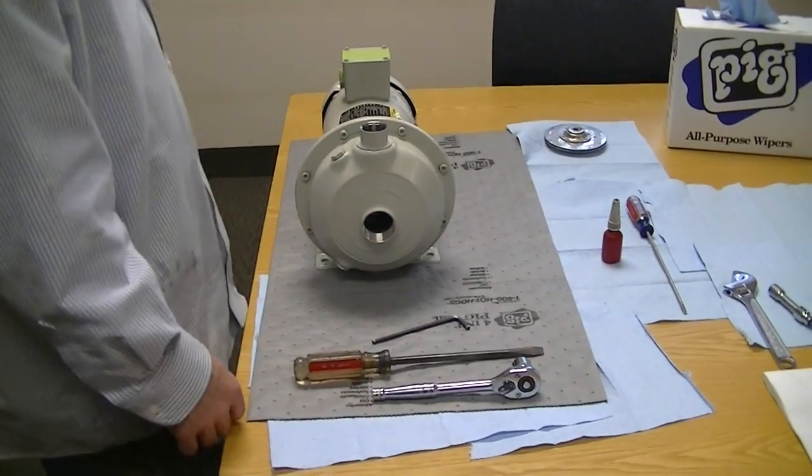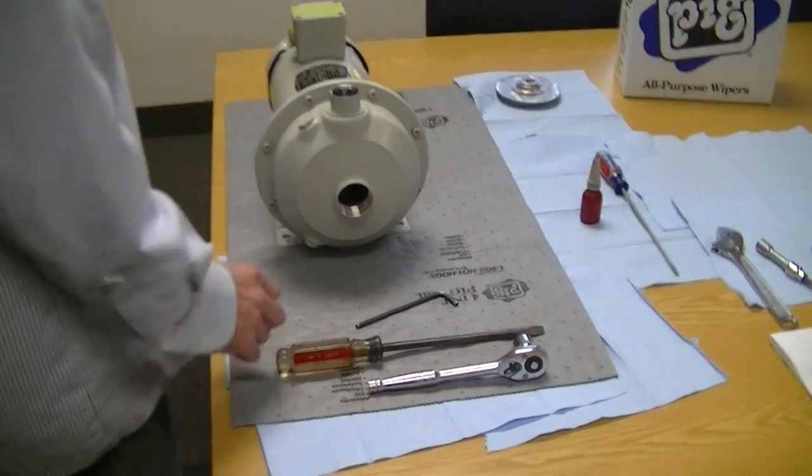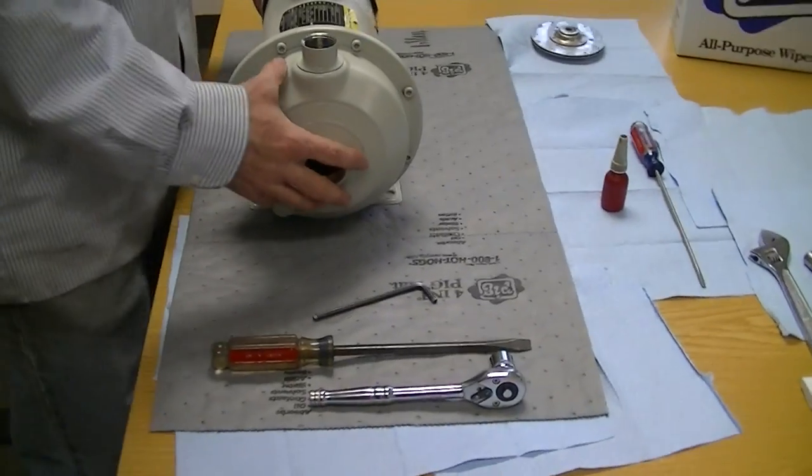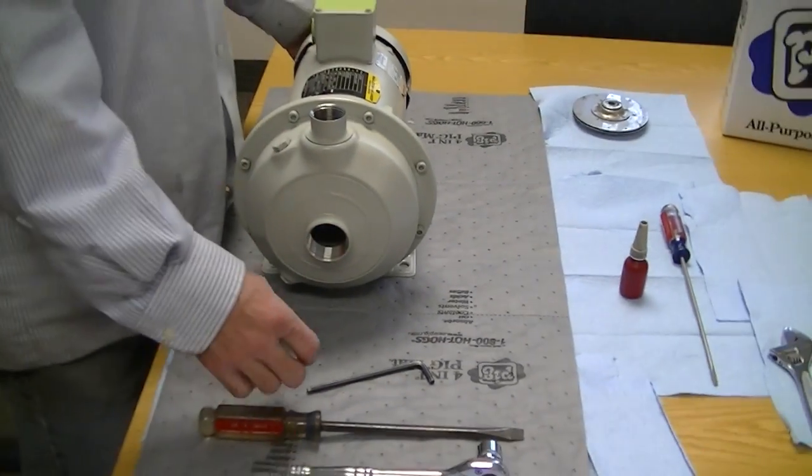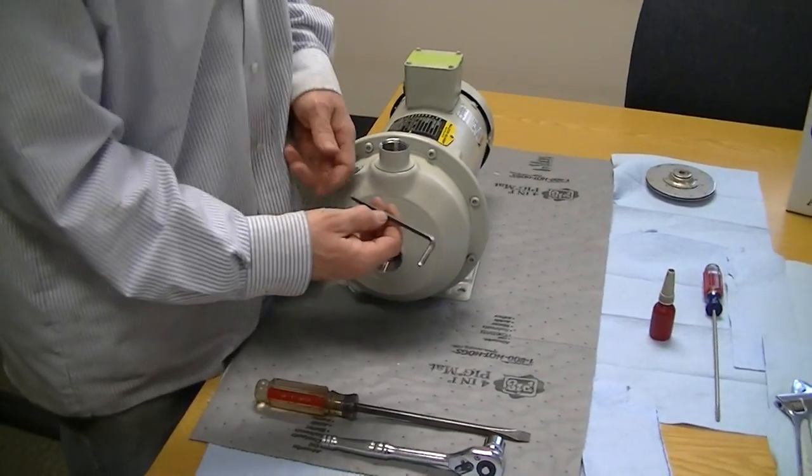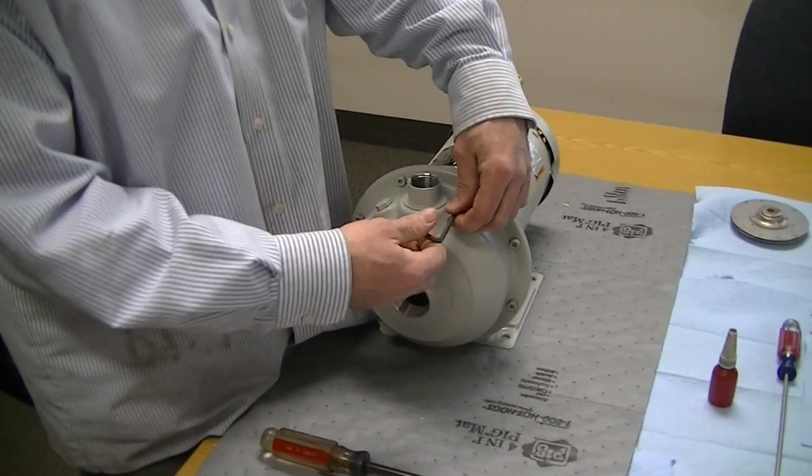I'm going to show you how to disassemble a Gould's NP pump to replace a shaft seal and/or impeller. First thing I'm going to use is a 5mm Allen wrench for all your volute bolts.